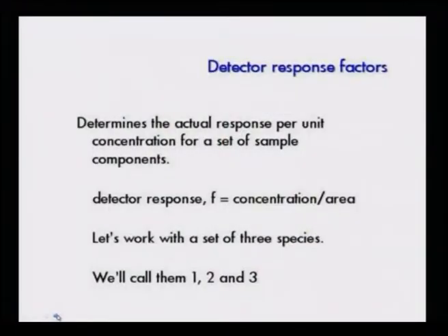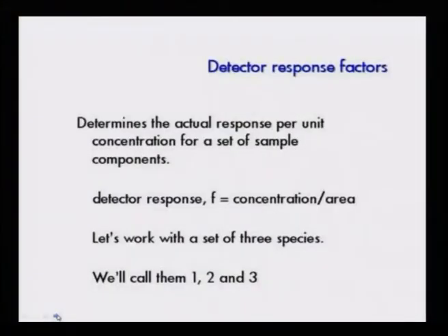Detector response factor is a very important factor. Why? Because the detector is the heart of a machine. That is what actually diagnoses whether the compound is present or absent, and determines the actual response per unit concentration for a set of sample components. That is why, for a machine to be working in proper condition, it is important to check the detector response, which means concentration over area.